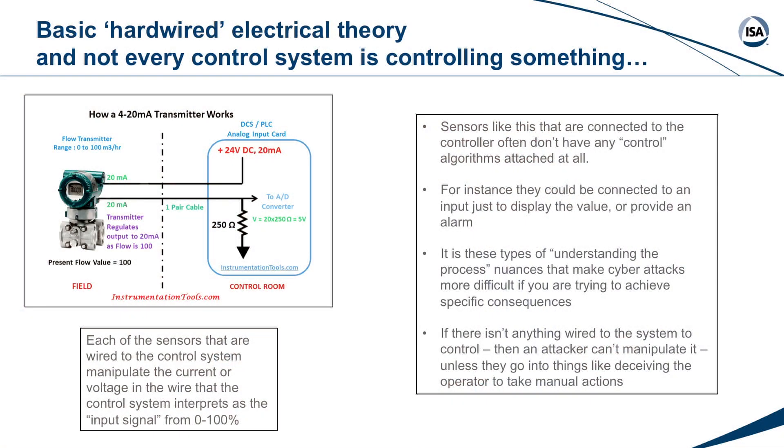The corollary to that in a current loop became 4 to 20 milliamps. So in a loop, we used current because then you could detect if the wire got broken. If you used voltage and you had 0 volts be the 0% signal, if the wire got broken, the control system would just say, oh well it's just reading 0. In a 4 to 20 milliamp system, if the system has 0 in it, it means there's a fault or a break.